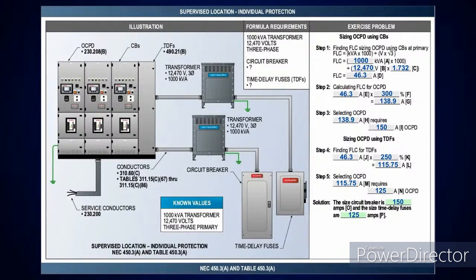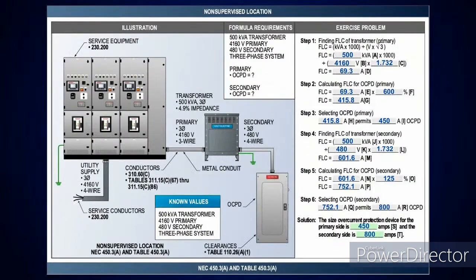That's not hard. All you had to do is look at this table. See, I'm in a supervised location, I didn't have any impedance, come across, look at my percentages, and go from there. That should be easy for everybody to follow. One thing I want to point out is I'm going to do multiple calculations here on transformers of different types, but you're going to notice I do not change the format of my calculation.